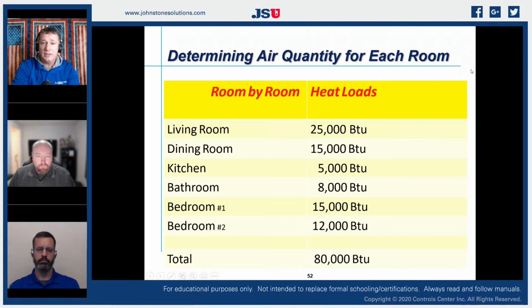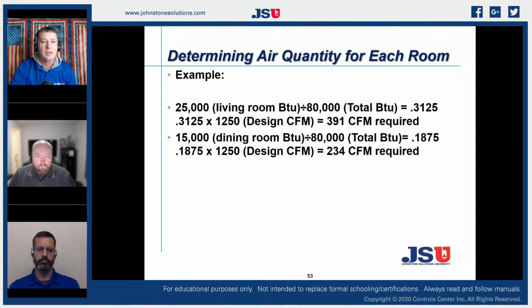All of this presentation comes from a heat load and duct design calculation class that we do, and it's typically a 2 to 3 hour class. So we're just hitting the highlights of it. But essentially, that's all we're going to do: room load divided by total load. It's going to give us a fraction, and we can multiply that fraction by the total CFM, and it'll give us our individual CFM.